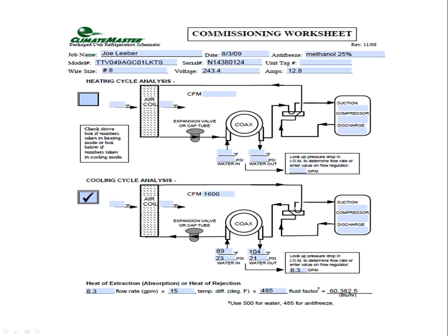So that's probably the direction I would go, is I would start to see, do I have the pump or pumps in line? Are they operating appropriately? Take those corrective actions that shows you, and then start this process over. Take these test readings again. You never know. You may find that someone put a valve in somewhere and it could be closed. So start to see where the fluid flow interruption is and make that correction, retest.